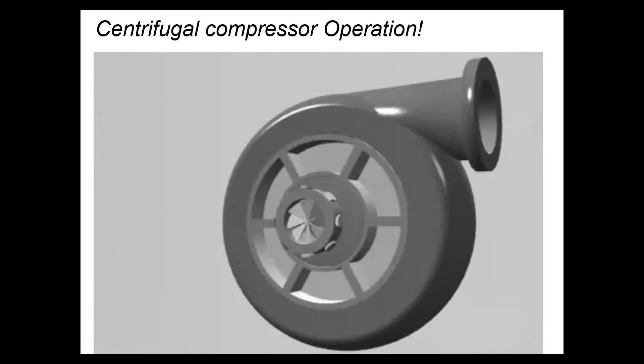Now I will talk about one important aspect. I spoke about a lot of things. We spoke about centrifugal force, we spoke about high head surge, we spoke about lift, we spoke about tangential velocity. So centrifugal force would typically look like this. Refrigerant is flowing through the middle, and the tangential velocity is being imparted onto it, and it is coming out from the top. It's very simple. Now, what is high head surge? High head surge is something where your condenser is sitting at a higher pressure than the pressure that is being generated by the impeller or the centrifugal chamber.